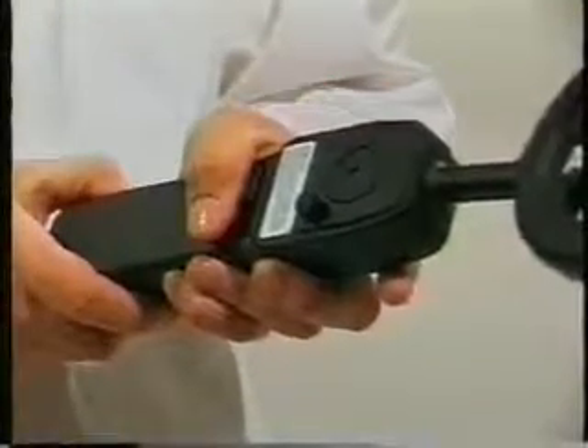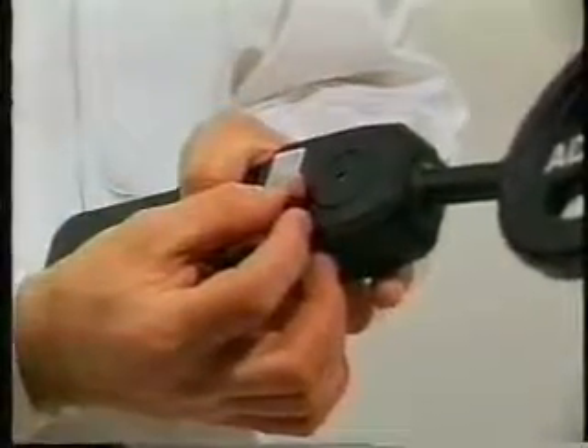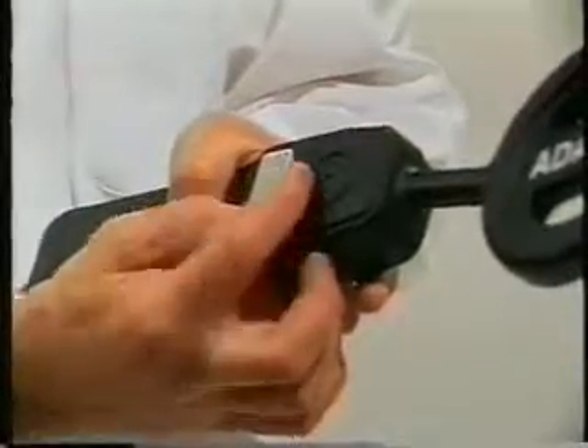Simply hold down the on-off button. When the unit gives the alarm signal, turn the sensitivity knob counterclockwise 4 full turns. Then release the button for a few seconds. Press the on-off button down again. If the alarm has stopped, calibrate the detector as normal. If the unit is still alarming, turn the knob another 4 full turns, or until the alarm stops. Then release the on-off switch for another few seconds. This procedure should be repeated until the unit can be calibrated as normal before use.